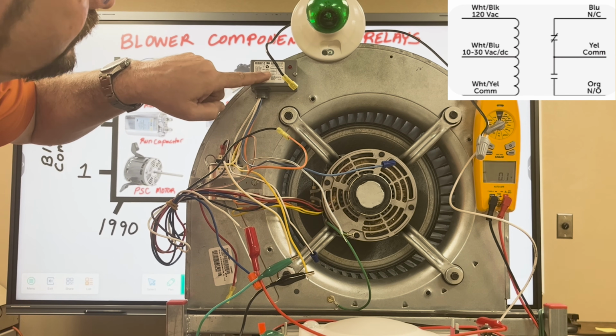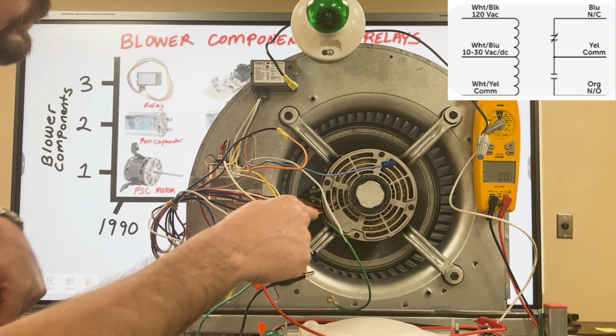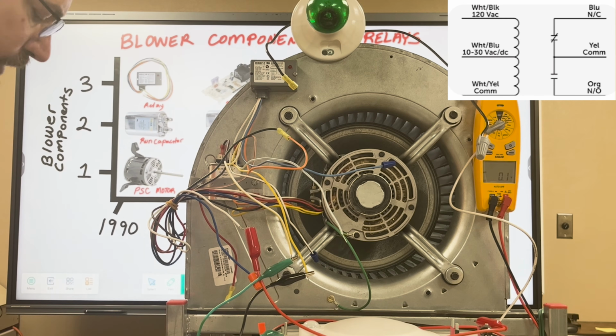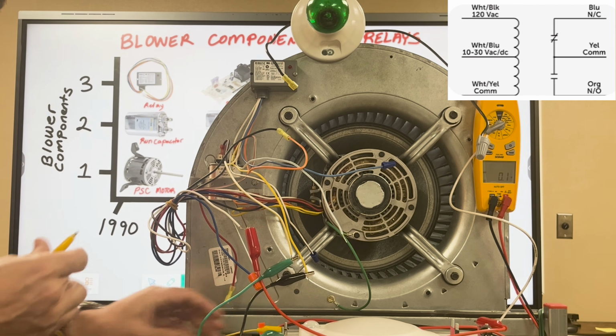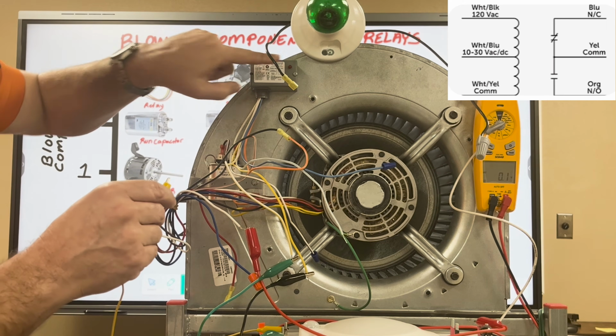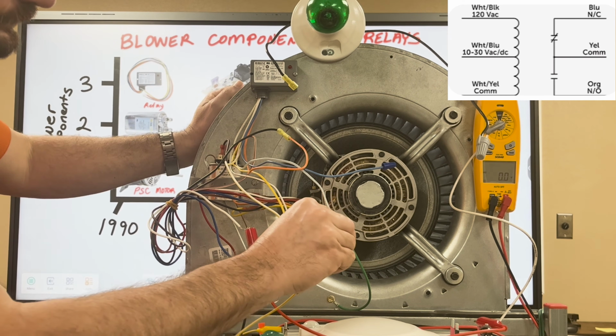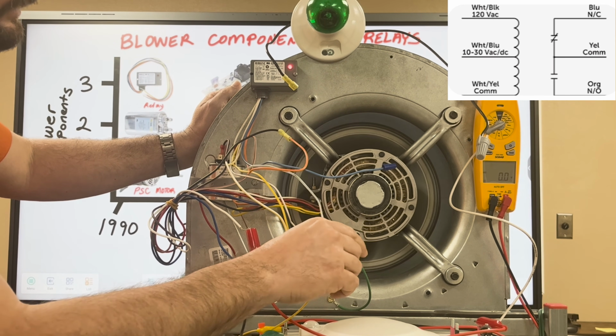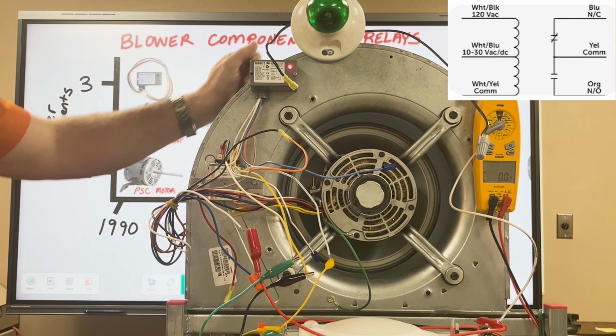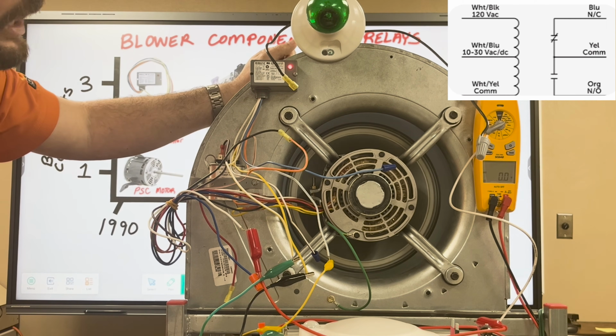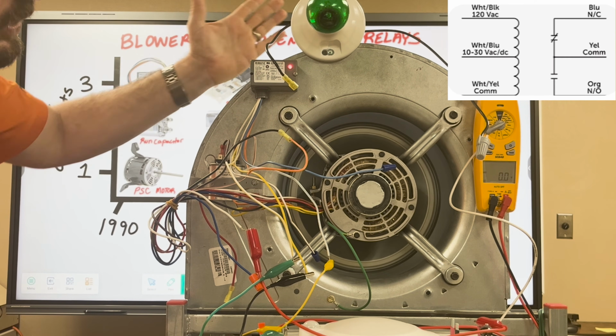And then I have white/blue, which is this one here hanging down. That'll be where I apply my 24 volts to that. So I'm going to go ahead and connect 24 volts there. You'll see the light come on and the motor will run. There we go. And this is how you would traditionally wire this up as a blower relay.